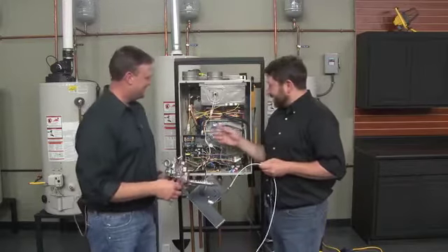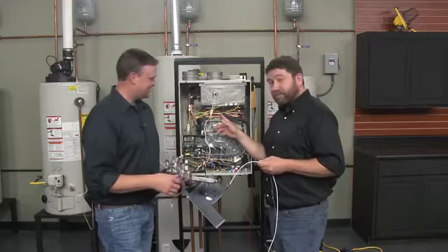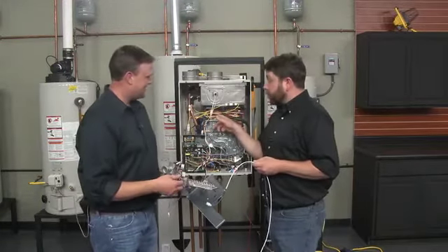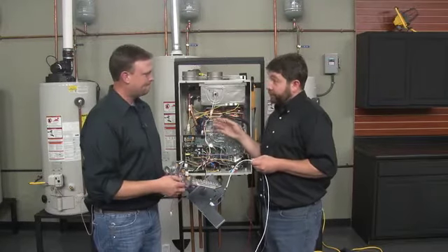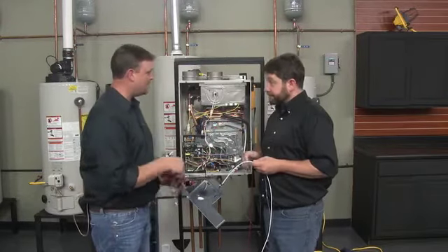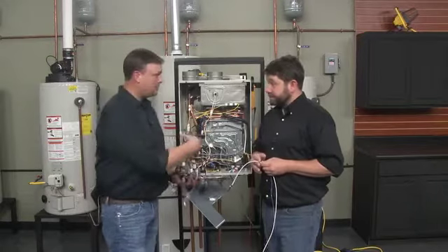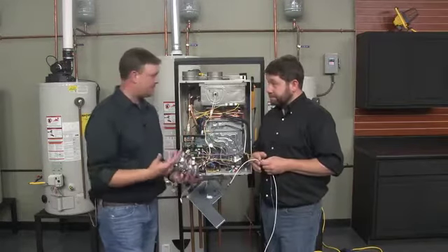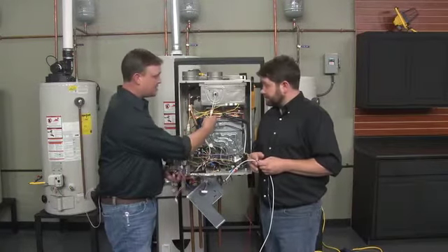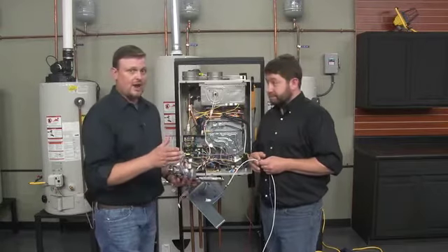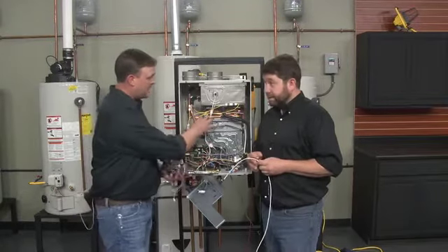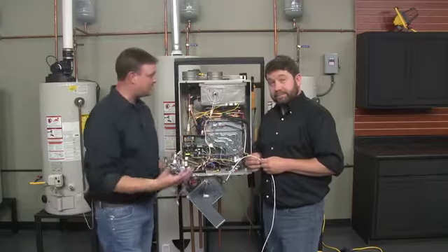Yes, I will. So that wraps around the heat exchanger. If there's a hole that gets put in the heat exchanger, somehow we get exhaust gases out. And that can happen, you get a hole because of the buildup on the inside. Those gases have got to go somewhere and create stress on this copper, and eventually you'll have a crack in there and you'll have a breach in the actual heat exchanger, allowing those flue gases to come out.